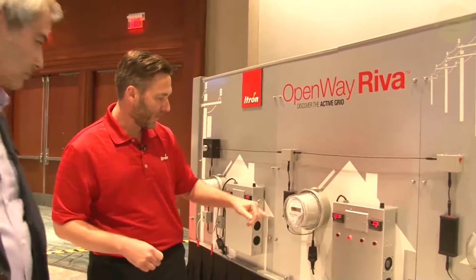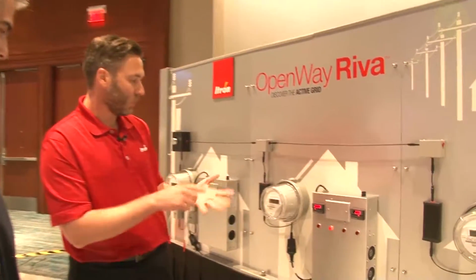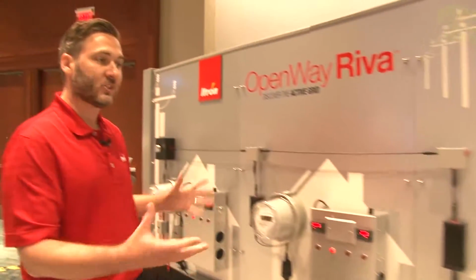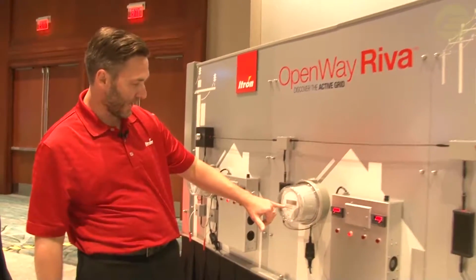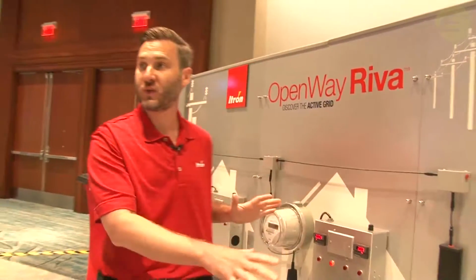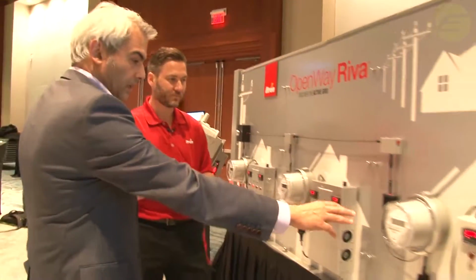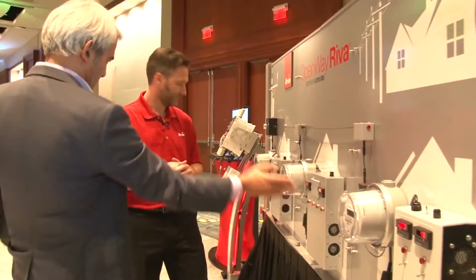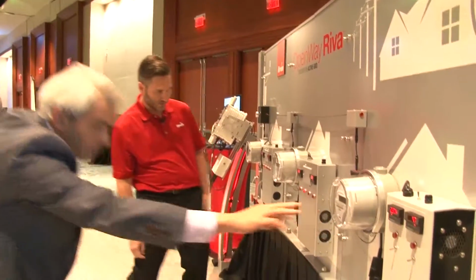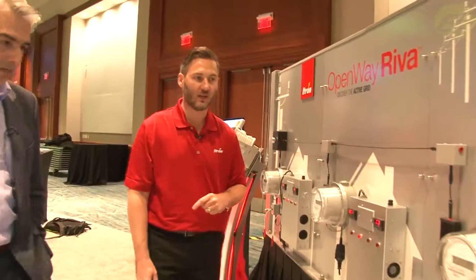Okay. So right now we've got each meter recognizing its individual load. 31 watts here. We've got about 5 watts here. And then they're also communicating with peer-to-peer communications, the community's summation. So they're adding up them all. And we have community load of 61 watts for the whole street. Okay, so let me replay that. You see each individual meter, but within the meter you also see the community load. Right. So you're saying this street of 3 houses in aggregate is at 68 watts. 68, yeah. So we're well under our transformer's rating right now. Right. Everything is hunky-dory.